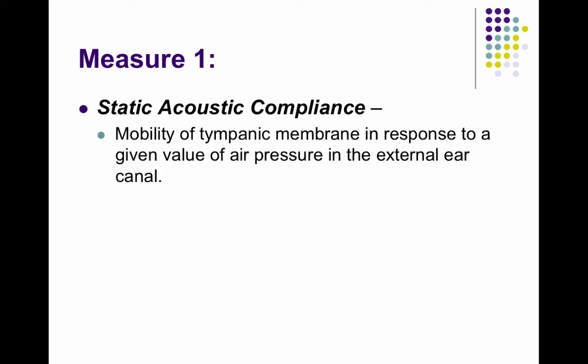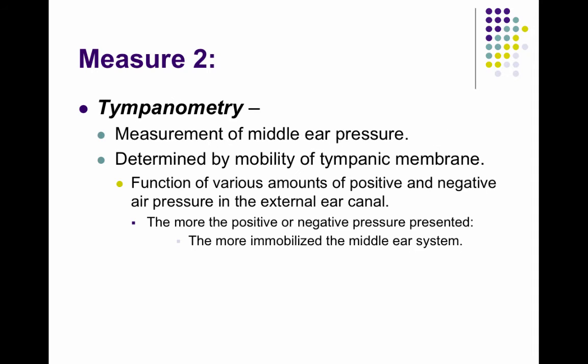The first measure is the static acoustic compliance, which is the mobility of the tympanic membrane — or the eardrum — in response to a given value of air pressure in the external ear. A probe is put in the ear canal, an airtight seal is obtained, air pressure is applied, and we measure the compliance.